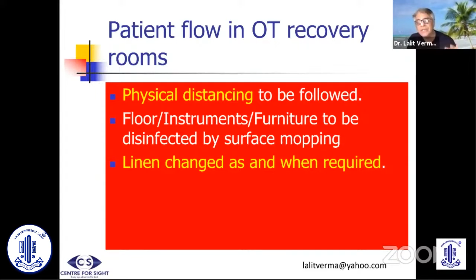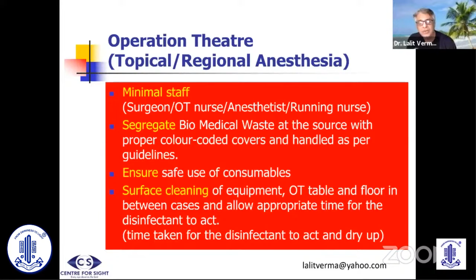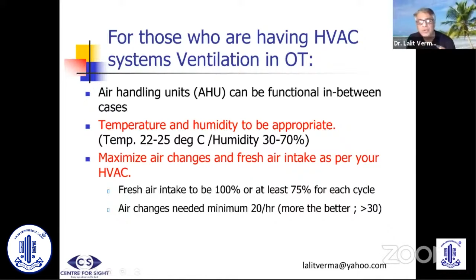In fact, we have not more than 30 to 40% staff we call, and segregate all the biomedical waste at source itself and ensure safe use of consumables. Surface cleaning of equipment has to be more often done than we used to do in the past. As far as air handling units and HVAC are concerned, we need to maintain temperature and humidity, and these are 22 to 25 degrees centigrade and humidity around 30 to 70%. Try to have maximum air exchanges and fresh air intake. Usually it is around 15 to 20, but more than 30 is recommended.